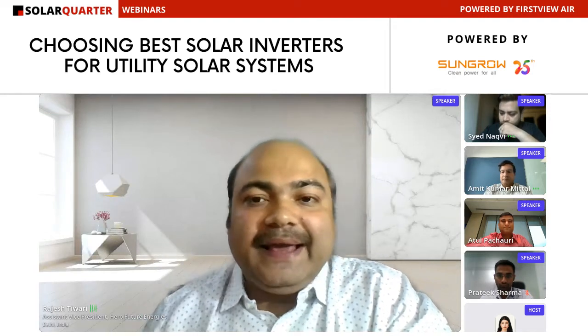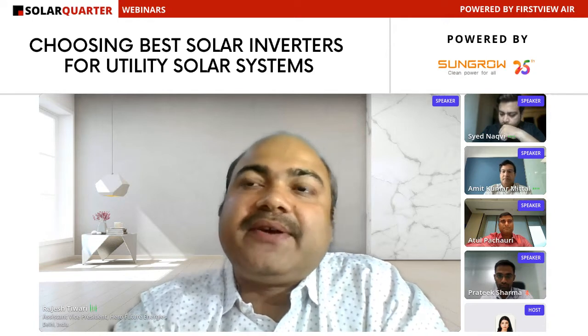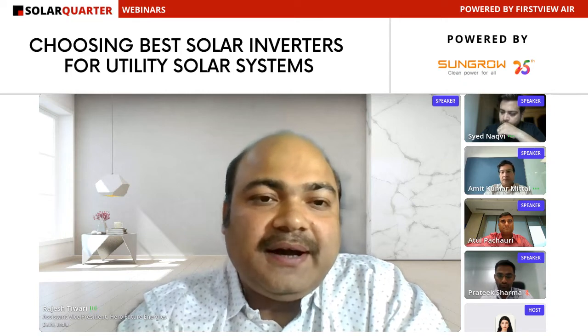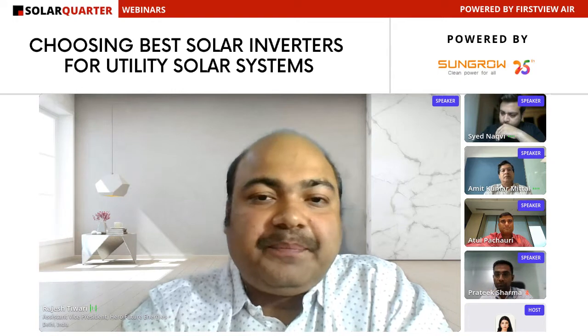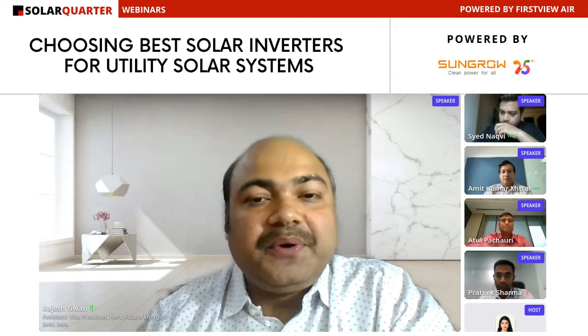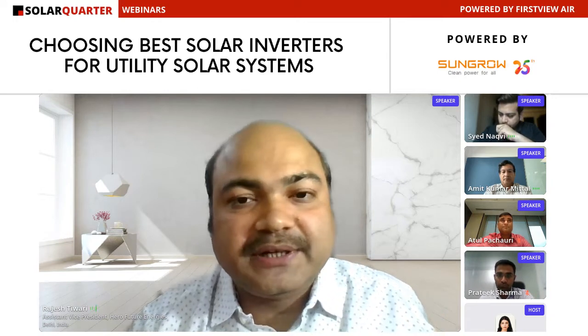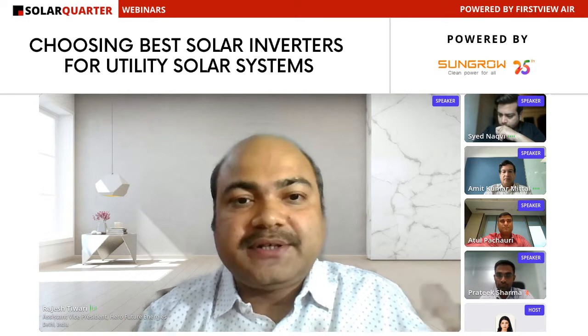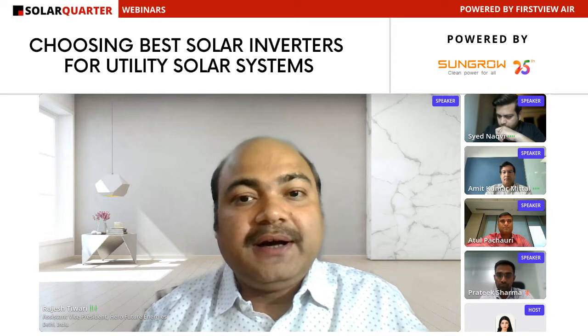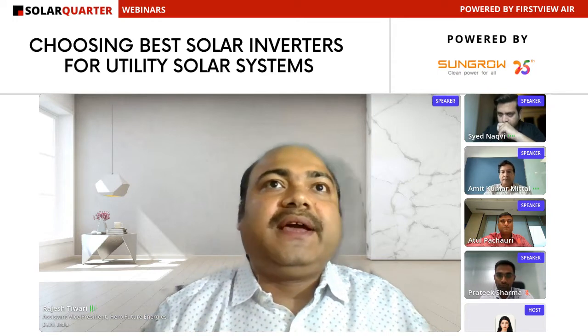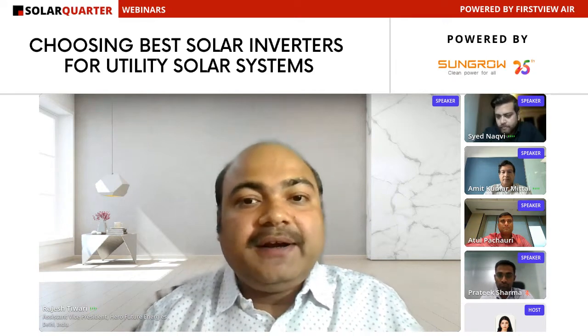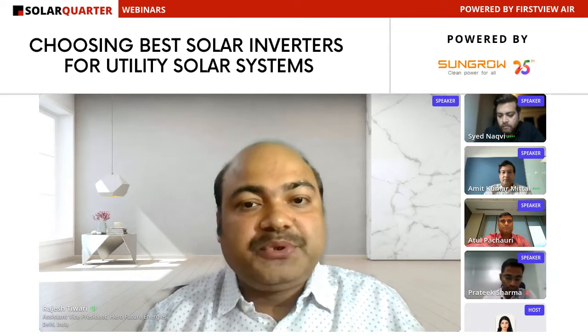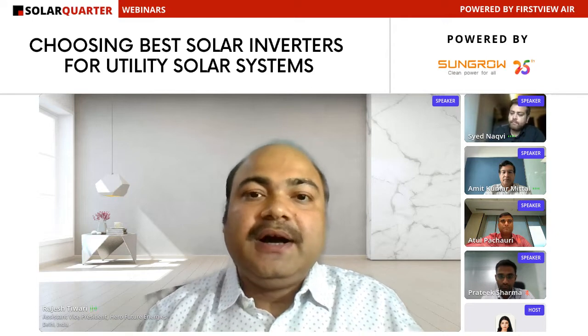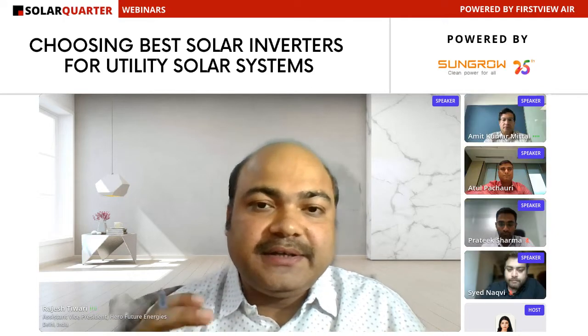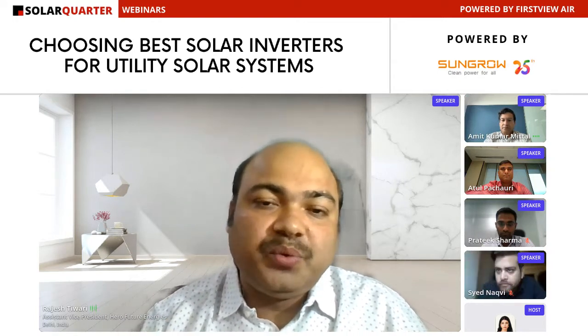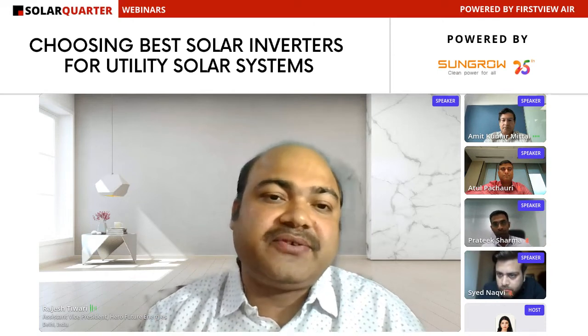In case of bifacial as well as tracker systems, this all depends on the geographical factors, like the undulation mentioned earlier. Nowadays, if you're dealing with a big scale project, say a 1.2 gigawatt single solar park, you require a huge amount of land - more than 4,500 acres. And in that 4,000-plus acres, you can't maintain a complete flat terrain. So you have to consider the cables, the designing of various types of modules to be configured with your central inverter or string inverter, and their compatibility.